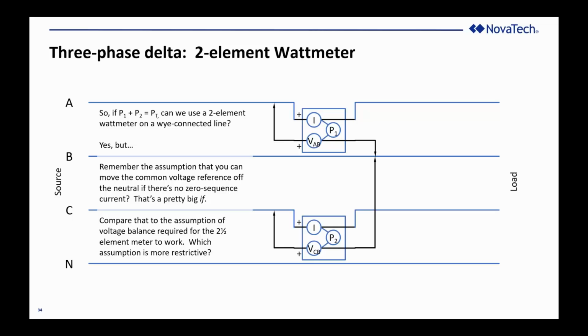The expectation of voltage balance, particularly in high voltage lines, is a reasonable assumption. But the expectation of current balance, particularly when we distinguish negative sequence from zero sequence imbalance, the assumption that you will have no loads that cause the current to have zero sequence imbalance, I think, is not usually a safe assumption as long as there's a neutral conductor to carry it. If there's no neutral conductor to carry it, you've got a delta-connected line, which is why 2-element wattmeters can be used on delta-connected lines.